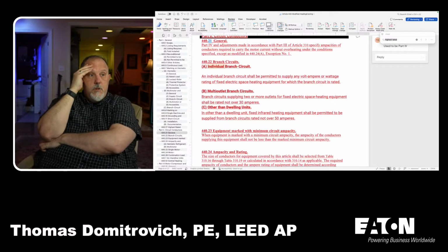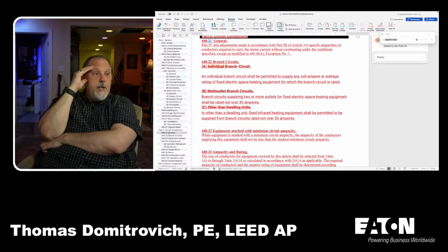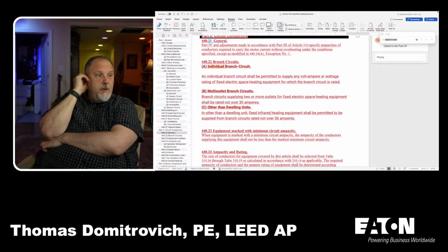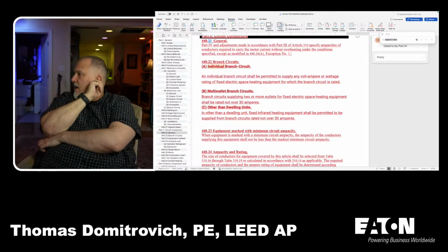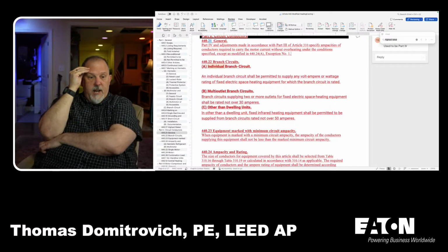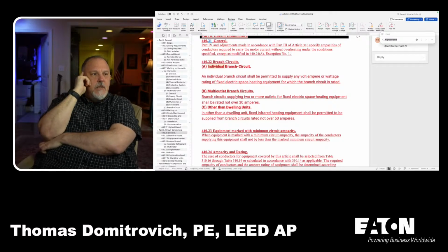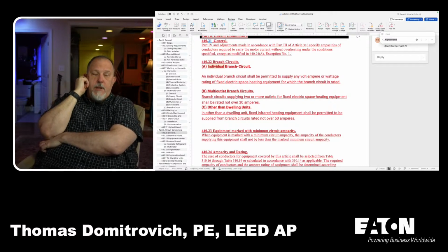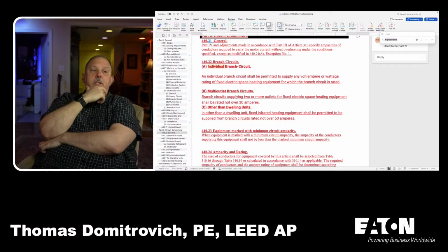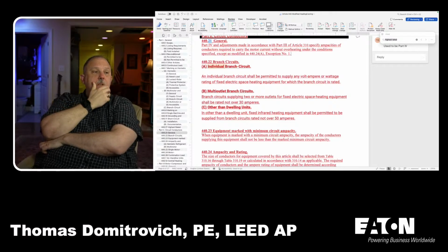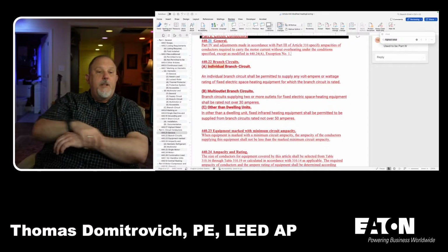440.22, branch circuits. An individual branch circuit shall be permitted to supply any volt, ampere, or wattage rating of fixed electric space heating equipment for which the branch circuit is rated. Multi-outlet branch circuits: branch circuits supplying 2 or more outlets in other than dwelling units. In other than a dwelling unit.